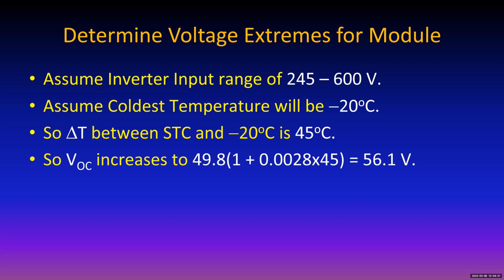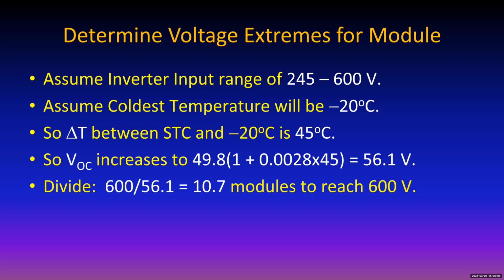49.8 is the standard test condition open circuit voltage of the module. And the 0.0028 is the temperature coefficient. And the 45 degrees is the difference between standard test conditions and the outdoor ambient, maximum value, 45. And so notice that the voltage goes up from 49.8 to 56.1, which stays below that 60 volt thing. But here's your formula for the people looking for the formula. Divide 600 by that, 10.7 modules. Well, you better not put in 11, better limit it to 10.